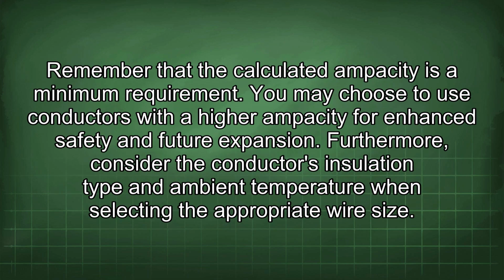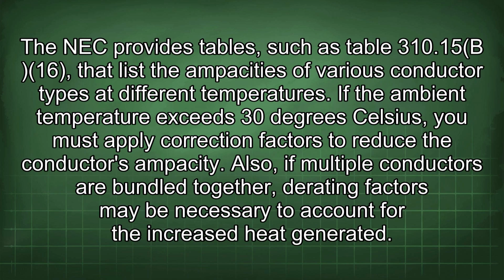Remember that the calculated ampacity is a minimum requirement. You may choose to use conductors with a higher ampacity for enhanced safety and future expansion. Furthermore, consider the conductor's insulation type and ambient temperature when selecting the appropriate wire size. The NEC provides tables, such as Table 310.15(B)(16), that list the ampacities of various conductor types at different temperatures. If the ambient temperature exceeds 30 degrees Celsius, you must apply correction factors to reduce the conductor's ampacity. Also, if multiple conductors are bundled together, derating factors may be necessary to account for the increased heat generated.